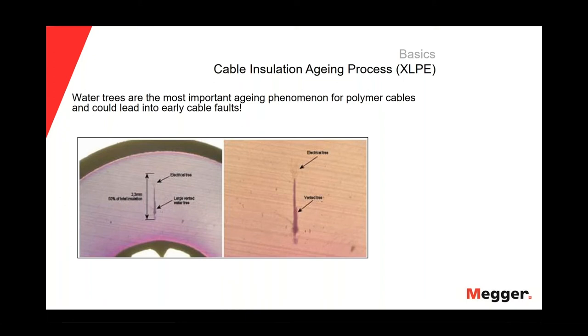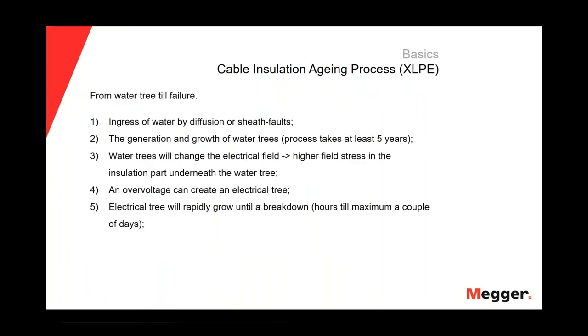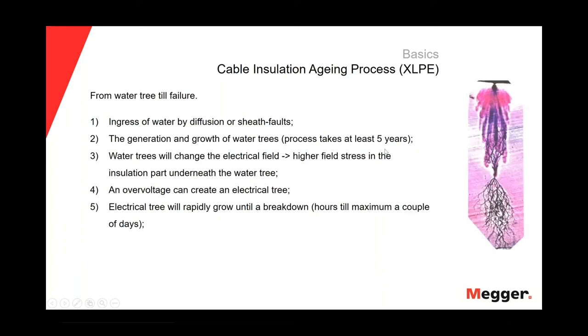So, to see the complete process of the insulation aging for XLPE cables, we could say that we will start with the ingress of water by diffusion or sheath faults. Then we will have the generation and growth of water trees. This process will take at least 5 years, okay? And then when the water tree reaches a critical size, maybe an overvoltage can create an electrical tree underneath of the water tree. And we will start first with a partial discharge process, and then we will have an electrical tree. And once we have an electrical tree in the insulation of the cable, it will take hours, maximum a couple of days, to have a fault.